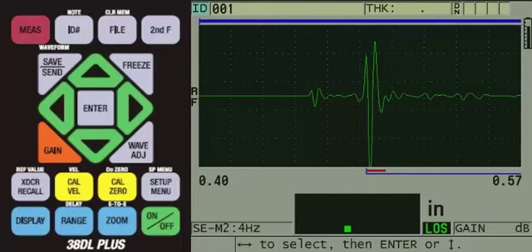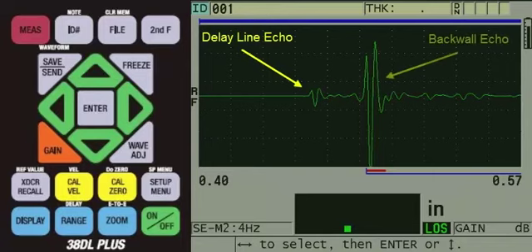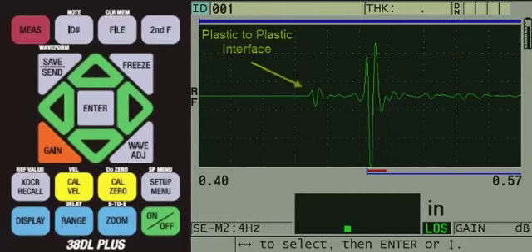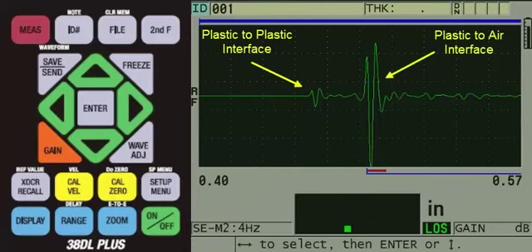We do not get a reading, and we observe a delay line echo which is lower in amplitude than the backwall echo on screen. Olympus thickness gauges use automatic gain control for the amplitude of the backwall echo. Therefore, the backwall will appear as 80% screen height. The delay line echo, by comparison, is much lower in amplitude because of the impedance matching between the plastic delay line and the plastic surface of the tubing sample. The backwall echo, which represents a plastic-to-air interface, has a larger impedance mismatch, and therefore a larger echo amplitude.